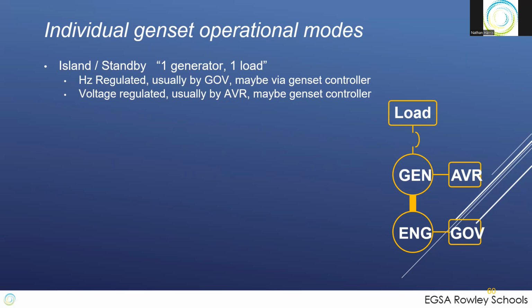So in individual operational modes, you can have island or standby. The gen is usually AVR controls the generator voltage, governor controls the speed, and you feed a load. Very simple, right down to a little pull start generator you buy at your hardware store. This is an island, right? This is an individual island mode.